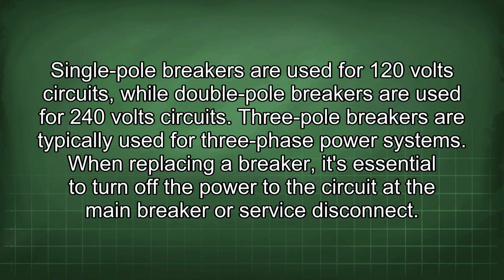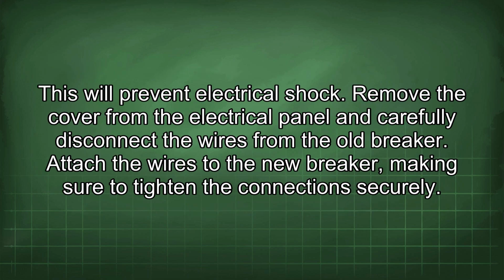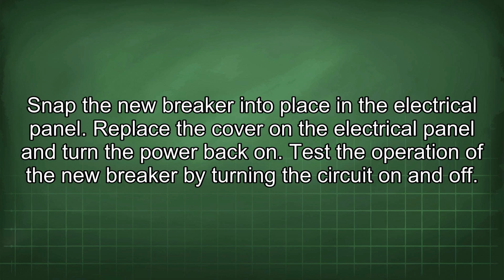When replacing a breaker, it's essential to turn off the power to the circuit at the main breaker or service disconnect. This will prevent electrical shock. Remove the cover from the electrical panel and carefully disconnect the wires from the old breaker. Attach the wires to the new breaker, making sure to tighten the connections securely. Snap the new breaker into place in the electrical panel. Replace the cover on the electrical panel and turn the power back on. Test the operation of the new breaker by turning the circuit on and off.